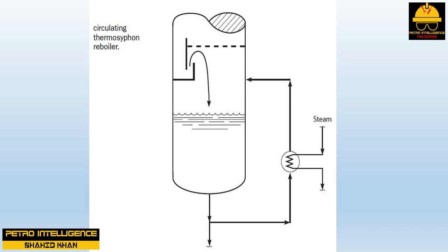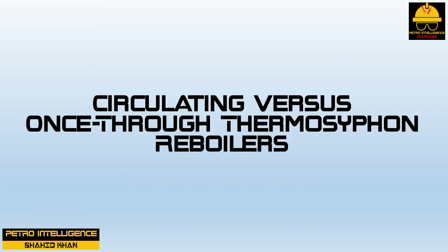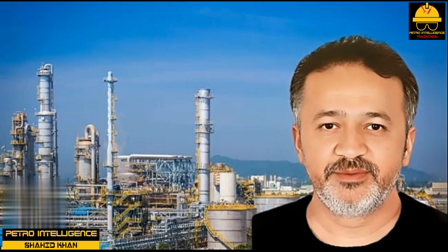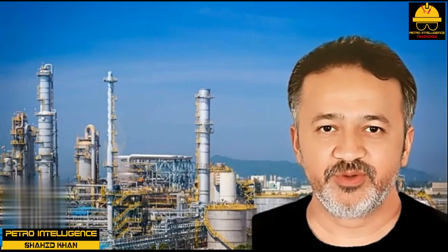However, should the tower bottom liquid level reach the reboiler return nozzle, thermosyphon flow will be restricted or even stop. This will reduce the reboiler heat duty and cause the tower pressure to drop, sometimes causing the tower to flood.